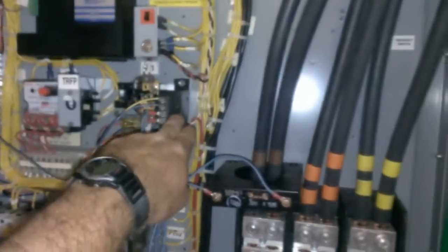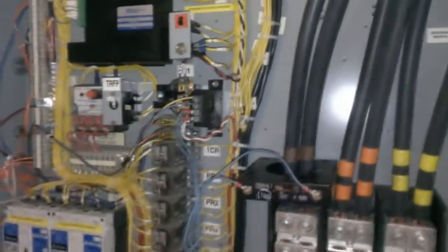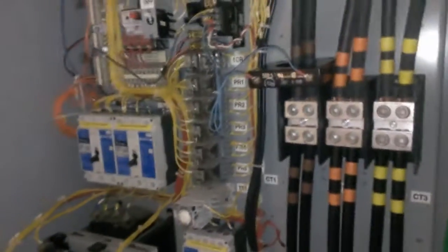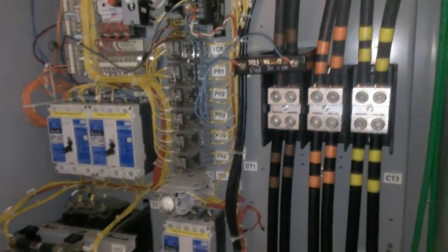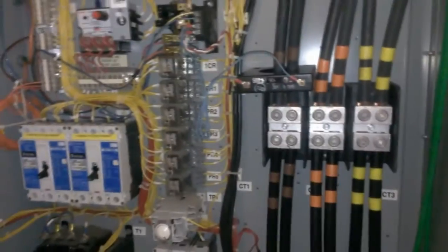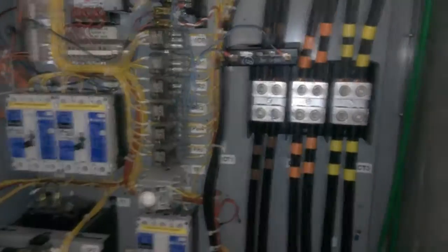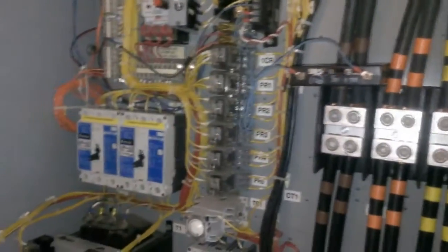And that's the schematic. So, I got those all put back right at the wires. They had the little converter here, zero to five volt output to read to the EMS computer. They had that hooked up to an amp meter on one of the wires on the motor side of the VFD. I don't think that would be right because you're going to get some crazy amps because it's VFD output. It'd be a nice big square wave, not a sine wave going. Well, I don't know what I should take that back because I actually have never put a scope on there to know how that VFD actually works.